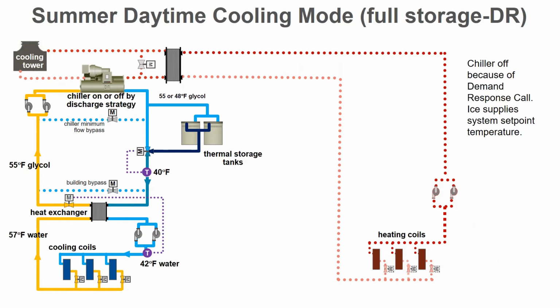Oops, I'm sorry. This was summer daytime cooling mode. This is without the chiller running. So now it's full storage. Maybe you'd be using this as a demand response situation where you want to turn the chiller off, and now the storage is meeting the load totally.